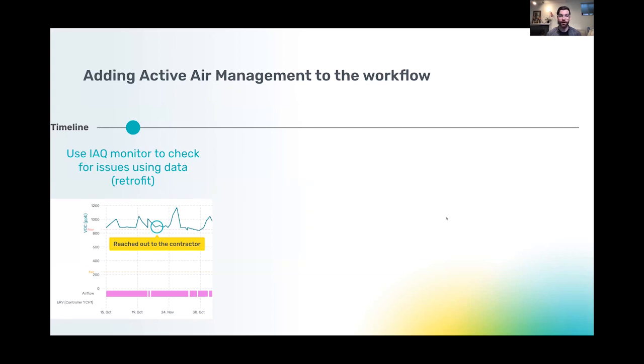We're doing something similar in indoor air quality, but this is even before that. How do we even diagnose the problem? How do we even choose the right pillar? Back to the point of all these issues of runtime and building envelope and climate zone, how do we actually select the right solution without having enough data? For example, data on the runtime, data on the chemical and particle levels happening in the home, data on how humidity is. And not only in the moment you're at the home, but what about how it changes during the nighttime? If they've got a setback, so it gets colder at night, what about on the weekends? What about as the seasons change?